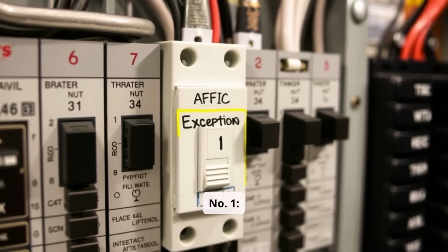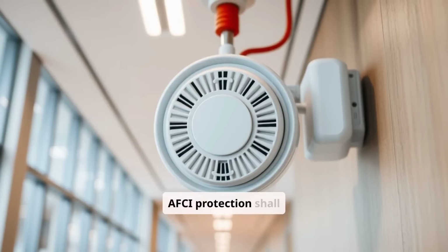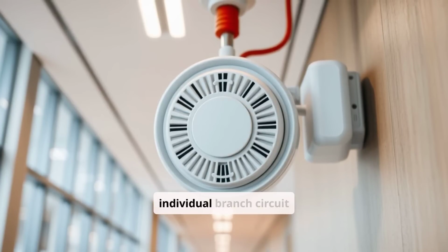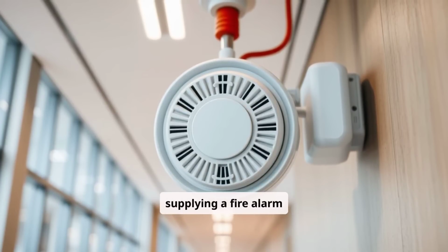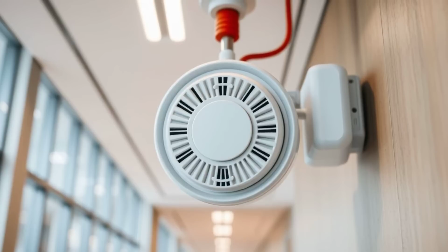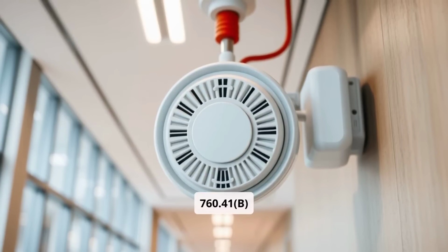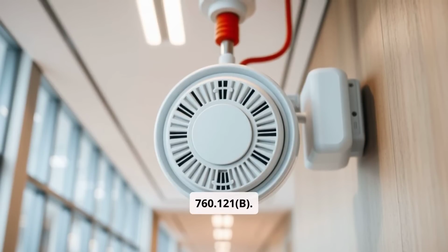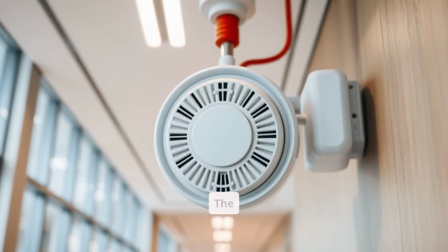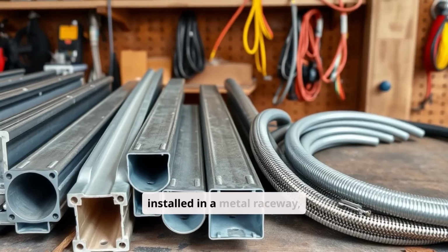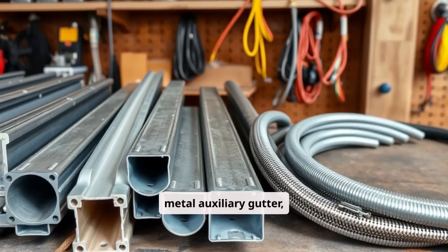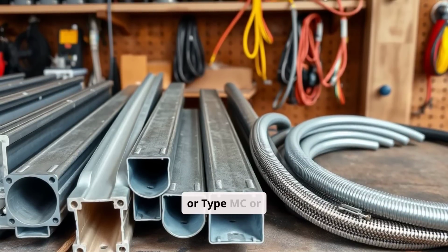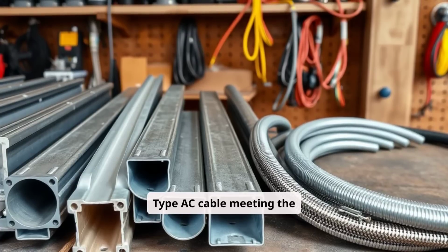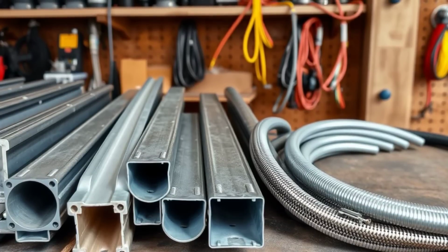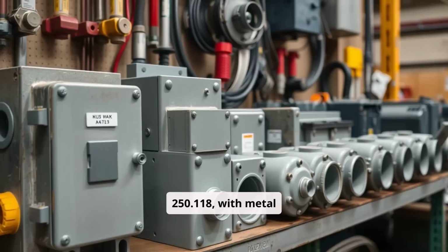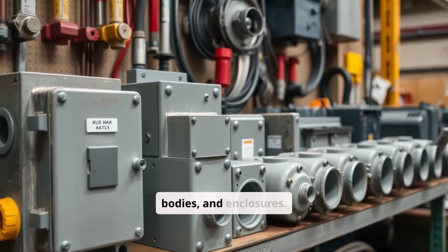Exception No. 1: AFCI protection shall not be required for an individual branch circuit supplying a fire alarm system installed in accordance with 760.41(B) or 760.121(B). The branch circuit shall be installed in a metal raceway, metal auxiliary gutter, steel armored cable, or Type MC or Type AC cable meeting the applicable requirements of 250.118, with metal boxes, conduit bodies, and enclosures.